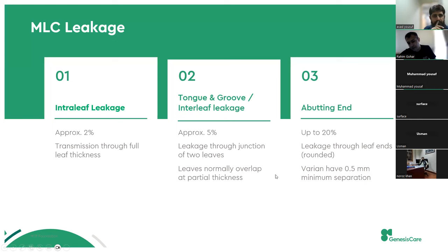Anyway, this is a kind of follow-up question, maybe. Why are Varian and Elekta using rounded leaves? What's the rationale behind it? Why are they not making them straight at the junction point? Rather, they're making them rounded to reduce the geometric or transmission penumbra. Yeah, transmission penumbra.